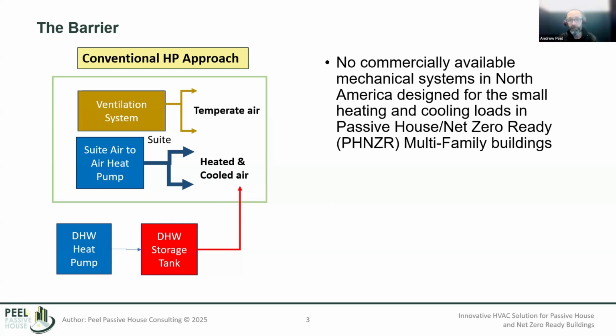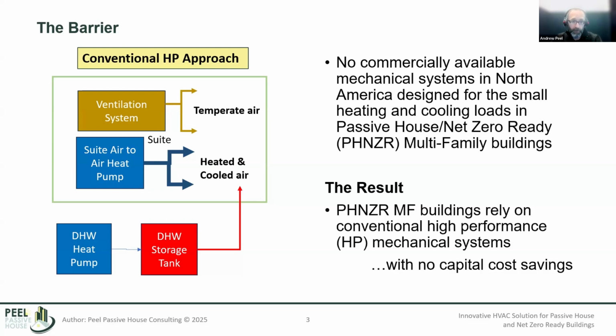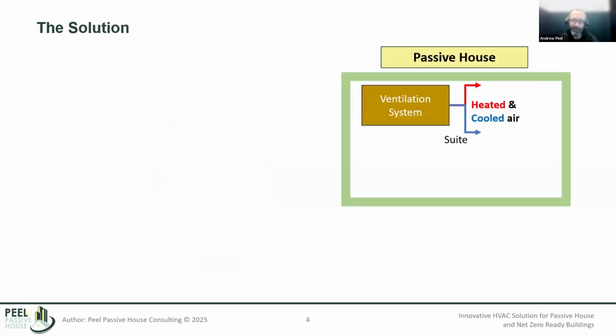And if we want to fully electrify, we have this additional heat pump—an air to water heat pump—typically to produce our hot water. All these systems typically aren't sized load-wise for the substantially decreased loads of Passive House net zero ready buildings. So we don't see any capital cost savings that we were promised with Passive House, particularly in multifamily.